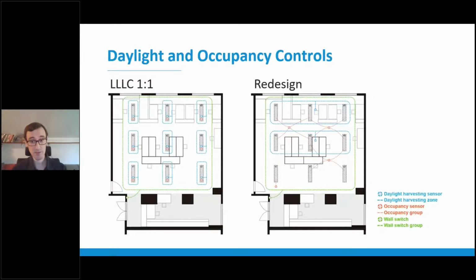The redesigned solution, on the other hand, used a zoning approach, which grouped luminaires into 3 zones. So we had the perimeter next to the north facade, we had the middle, and the core down along the south end. The core zone fell outside of what we consider the daylit zone, and as a result, it only included occupancy switching and not daylight harvesting in this case, while the perimeter and middle zones had their own zones with their own individual daylight sensors.